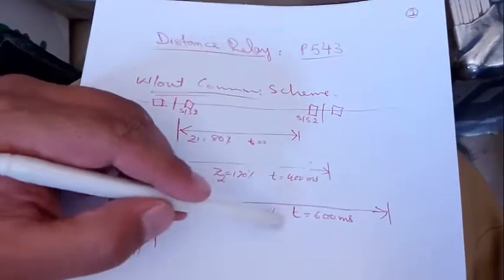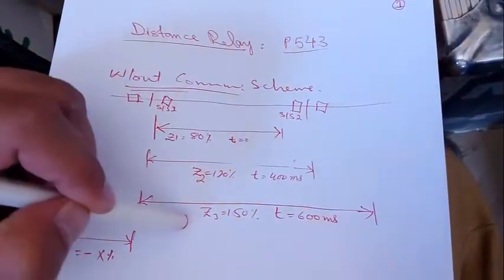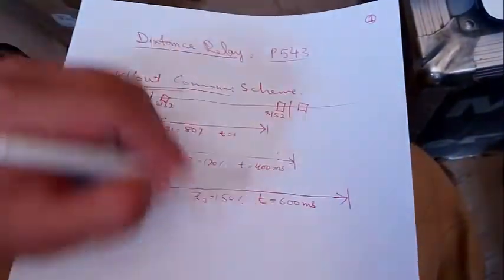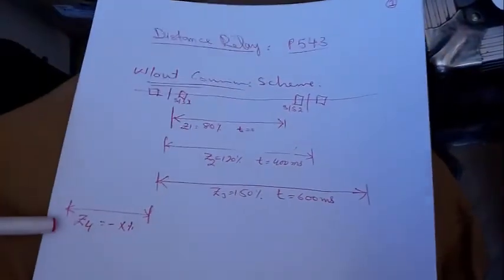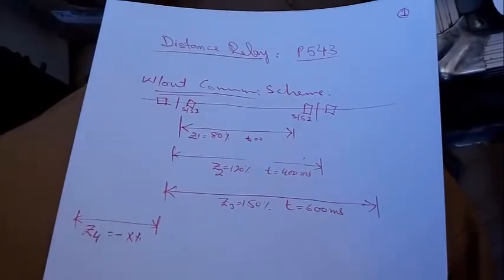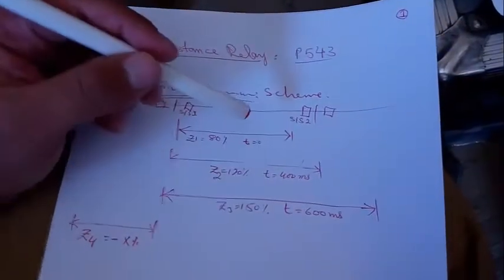If the fault is after 80% — around 90%, 95%, or 100% — the relay will trip in time zone two, after 400 milliseconds. If the fault is at 120% to 150% of the line, it falls in zone three and the relay trips after 600 milliseconds. These values are generally assumed values which can be set according to our requirements. Zone four is in the reverse direction. Now we will show how to draw these zones.